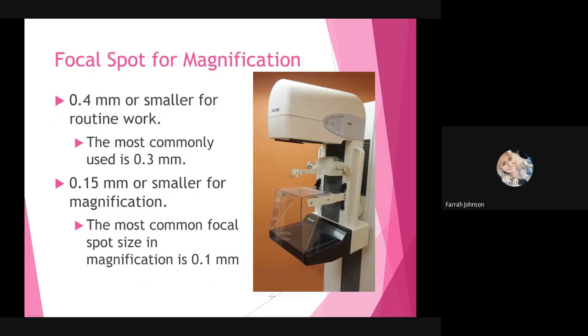So focal spots for magnification. For routine work, you can use a 0.4 millimeter or smaller. The most common is going to be the 0.3. For magnification views, you're going to use a 0.15 millimeter or smaller, but the most common focal spot size is going to be a 0.1 millimeter.